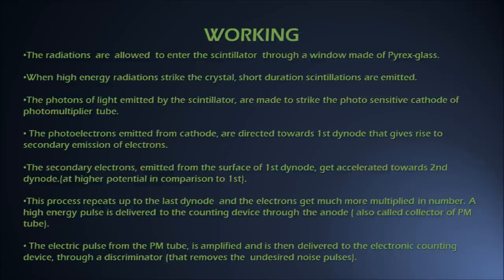The photoelectrons emitted from the surface of the cathode are directed towards the first dynode, giving rise to secondary emission of electrons with about zero velocity. The secondary electrons emitted from the surface of the first dynode get accelerated towards the second dynode, which is kept at higher potential in comparison to the first. This process repeats up to the last dynode, and the electrons get much more multiplied in number when they reach the anode. A high energy pulse is delivered to the counting device through the anode, which is also called the collector of the PM tube.